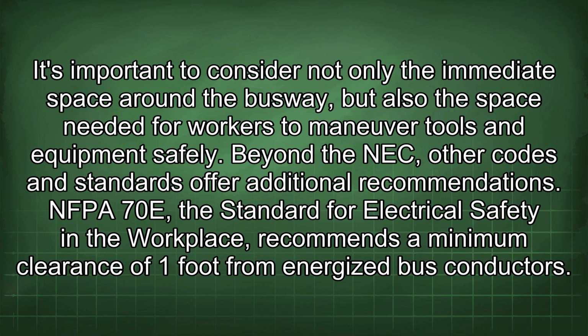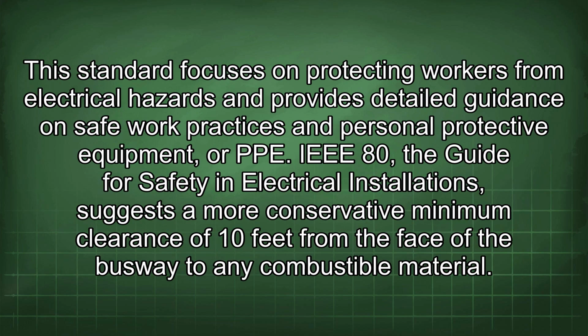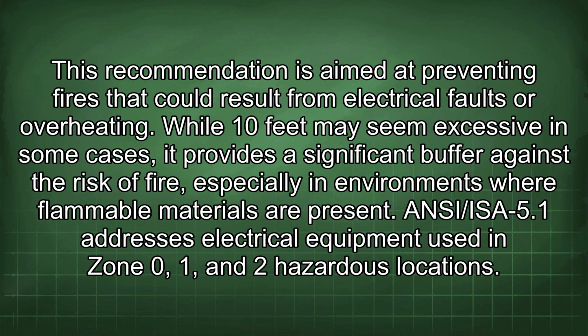Beyond the NEC, other codes and standards offer additional recommendations. NFPA 70E, the standard for electrical safety in the workplace, recommends a minimum clearance of 1 foot from energized bus conductors. This standard focuses on protecting workers from electrical hazards and provides detailed guidance on safe work practices and personal protective equipment, or PPE. IEEE 80, the Guide for Safety in Electrical Installations, suggests a more conservative minimum clearance of 10 feet from the face of the busway to any combustible material. This recommendation is aimed at preventing fires that could result from electrical faults or overheating. While 10 feet may seem excessive in some cases, it provides a significant buffer against the risk of fire, especially in environments where flammable materials are present.